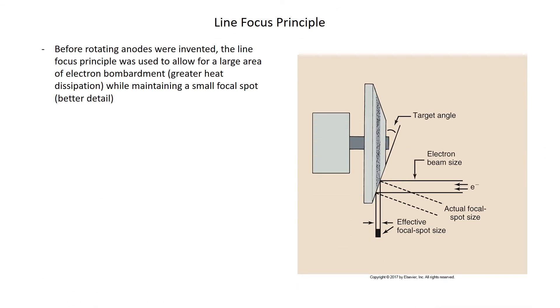The line focus principle is based on the fact that you can have a large actual focal spot, and because of the angle of the anode's face, you can have a smaller effective focal spot. The advantage is that the larger actual focal spot allows for greater heat dissipation, while the smaller effective focal spot gives you better detail. Before rotating anodes were invented, the line focus principle was used to allow for a large area of electron bombardment — greater heat dissipation — while maintaining a small focal spot for better detail.